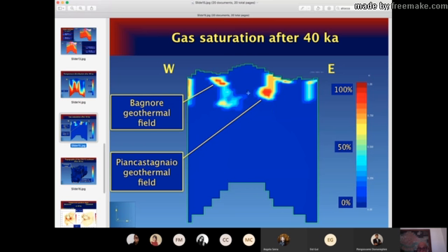Why I like to point this out to you is because gases are really what you don't want in a geothermal field. The reason is that gases do not condense. And if they do not condense, they cannot liberate enthalpy to produce a larger power of electric energy. In a water vapor geothermal field, like 90% of the energy is not brought to the surface through temperature, but through enthalpy.